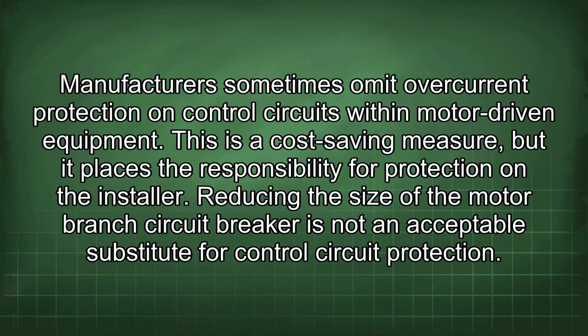Manufacturers sometimes omit overcurrent protection on control circuits within motor-driven equipment. This is a cost-saving measure, but it places the responsibility for protection on the installer.